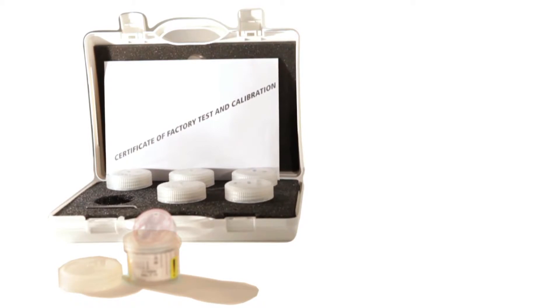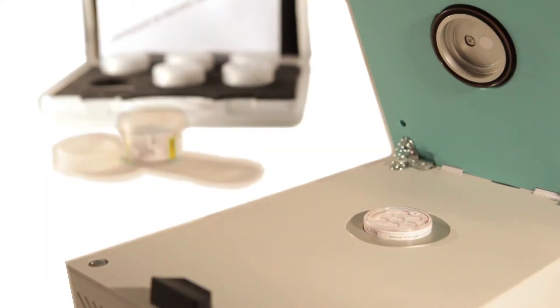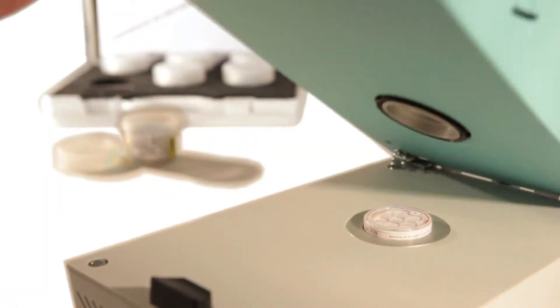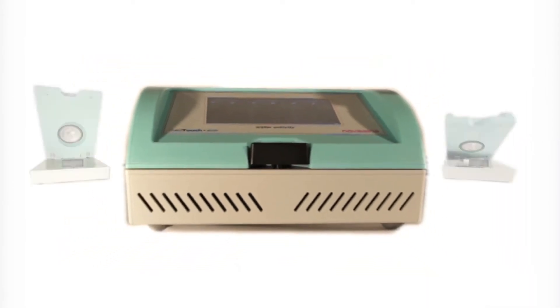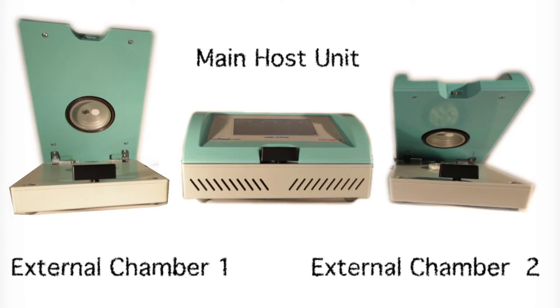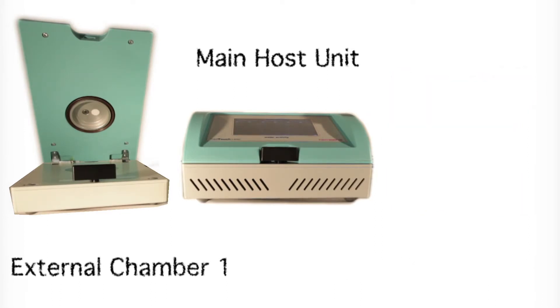Instrument calibration is performed using reusable Novasina humidity standards. These well-proven certified references are characterized by their accuracy, repeatability and durability. For extended measurement capacity, two external chambers can be partnered with the LabTouch. The complete system is then controlled by the main host unit.